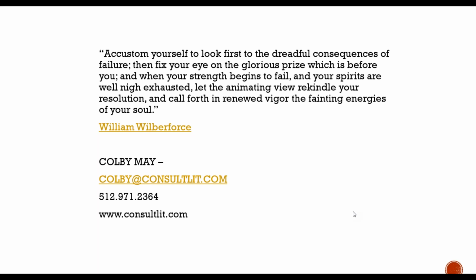But the payback, I mean, I hear you. You don't want to damage other equipment, right? But it's about exploring, like you said, thinking outside the box. If we're worried about it being too humid and affecting a grand piano, which is a concern, maybe that's when we work with our HVAC contractor and get a smaller system that is focused just in that area, or an internal dehumidification device in or around the piano. So it's worth it, because if it costs us $10,000 to run this equipment, but we can install a solution that's much more efficient for $4,000, we're already saving money. And many times there's a compromise point too.